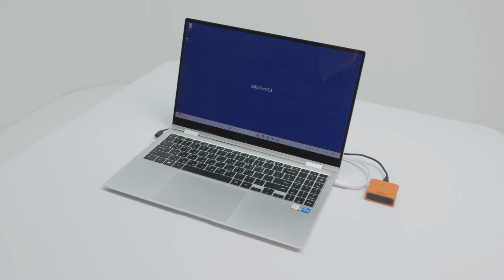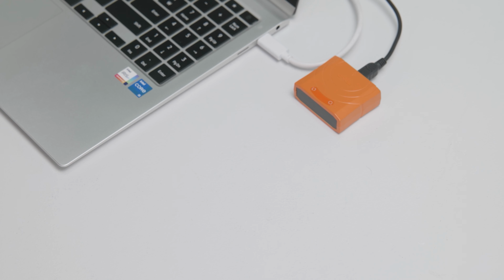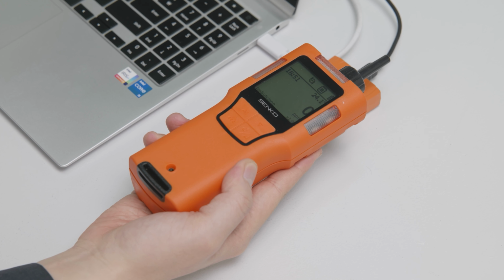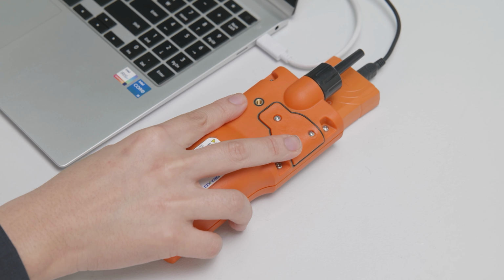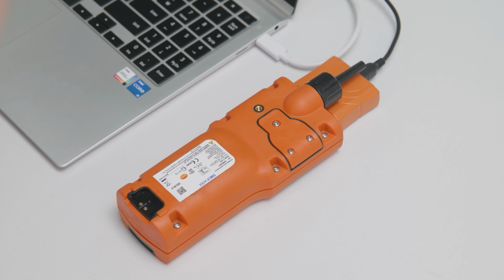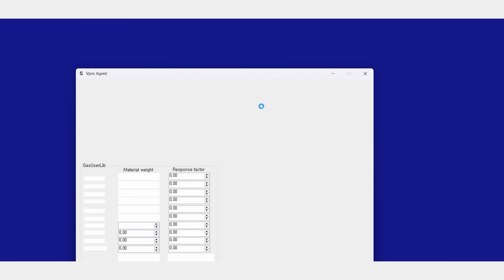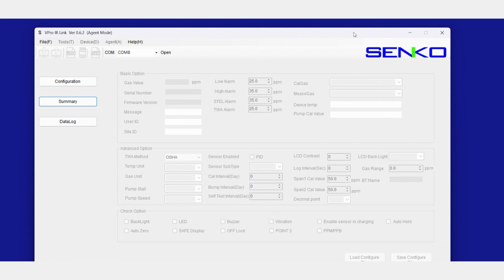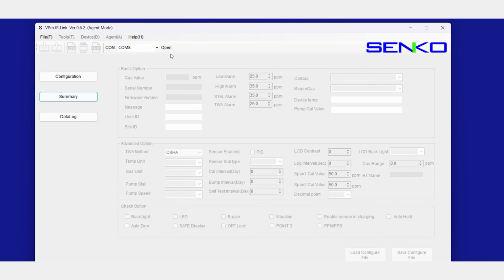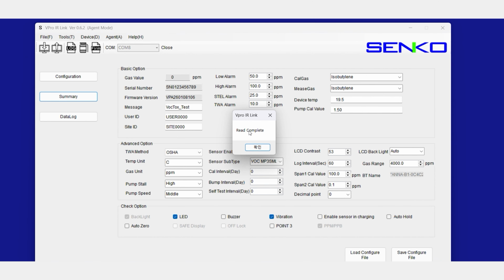IR-Link is a device that supports advanced settings and maintenance by linking vPro with a PC. To connect to the IR-Link, first align IR-Link with the device's IR port and then run the IR-Link software on the PC. It will automatically connect with the device. After connecting, you can efficiently manage key functions of vPro in a PC environment, such as settings management, zero and span calibration, data log checking, and firmware upgrades.